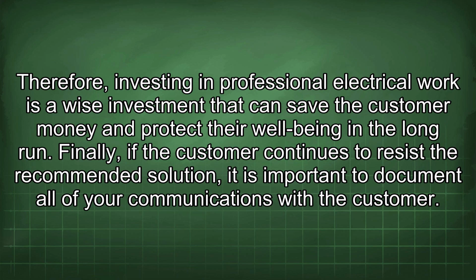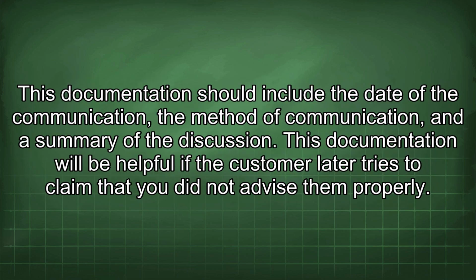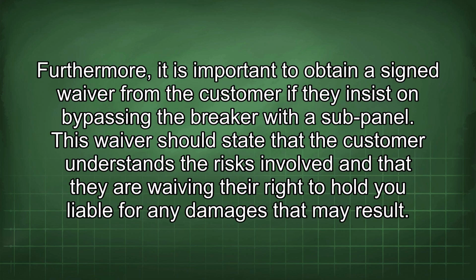of your communications with the customer. This documentation should include the date of the communication, the method of communication, and a summary of the discussion. This documentation will be helpful if the customer later tries to claim that you did not advise them properly. Furthermore, it is important to obtain a signed waiver from the customer if they insist on bypassing the breaker with a sub-panel. This waiver should state that the customer understands the risks involved and that they are waiving their right to hold you liable for any damages that may result.